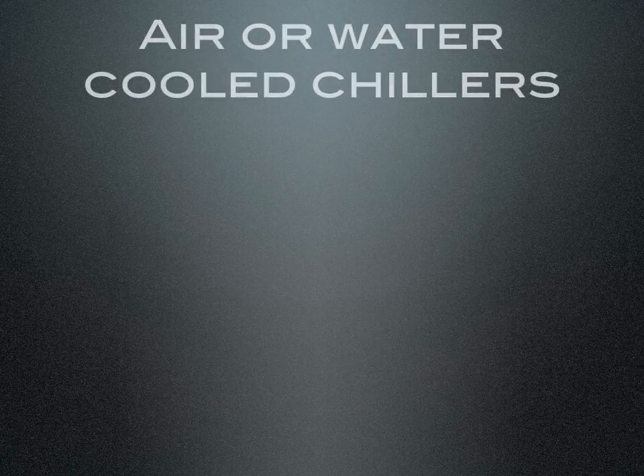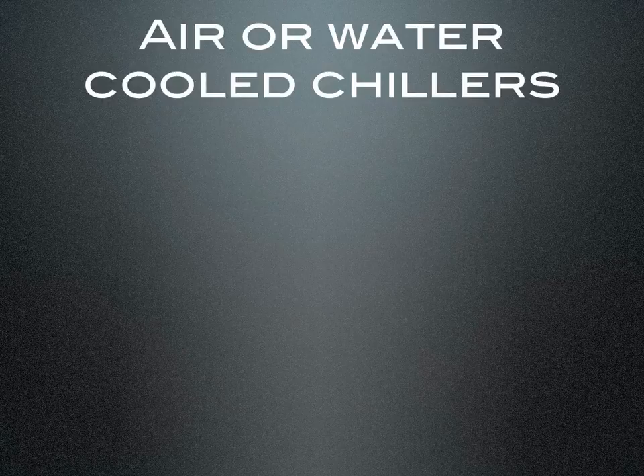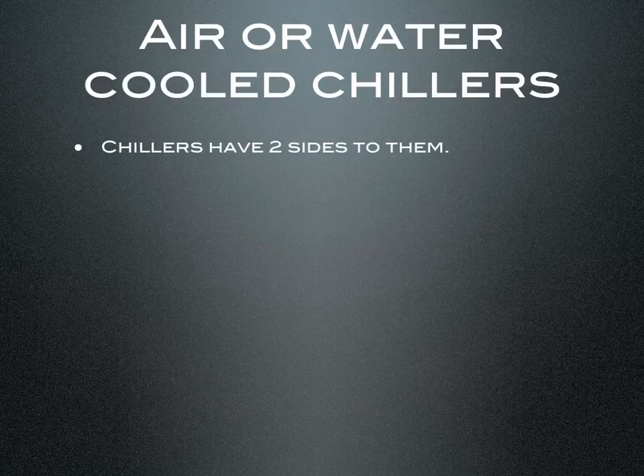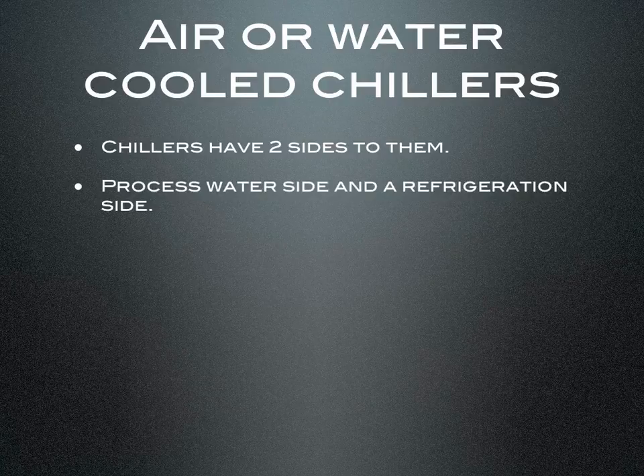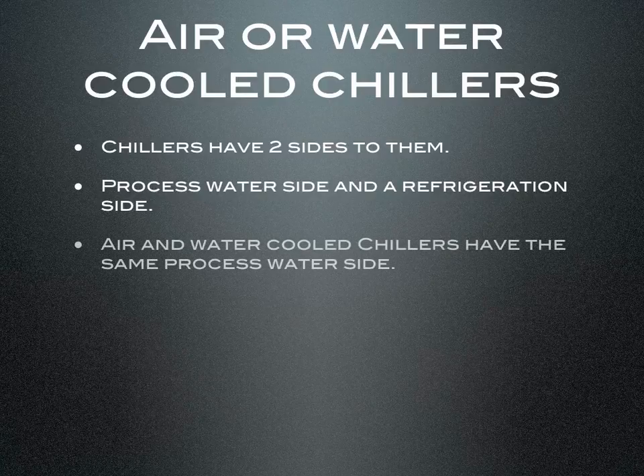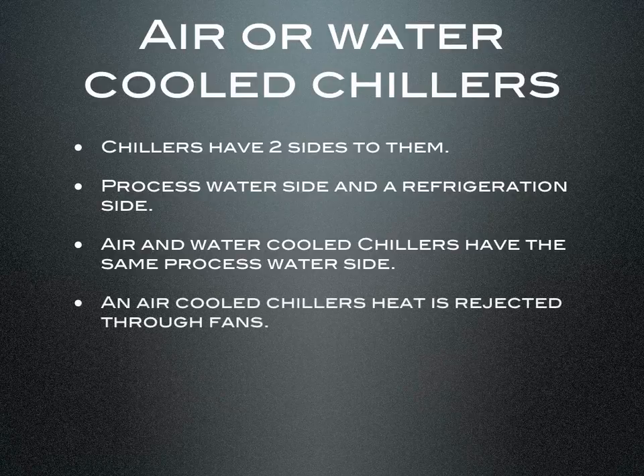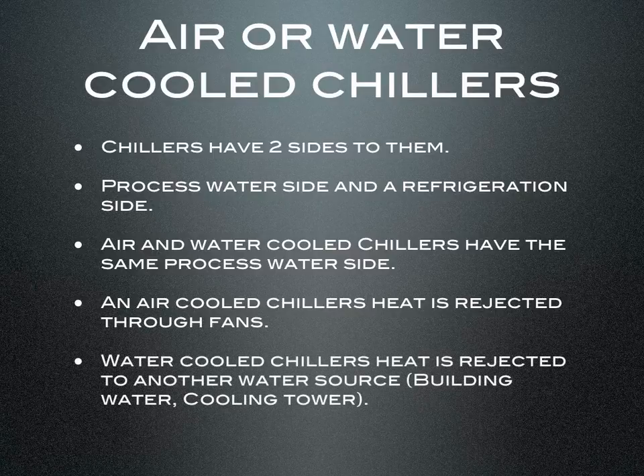Air or water cooled chillers — let's go over some of the comparisons and differences between the two. Chillers have two sides: a process water side and a refrigeration side. Air and water cooled chillers have the same process water side. An air cooled chiller's heat is rejected through fans, while a water cooled chiller's heat is rejected to another water source such as building water or a cooling tower. There's really not much of a difference — it's basically just how the heat is rejected.